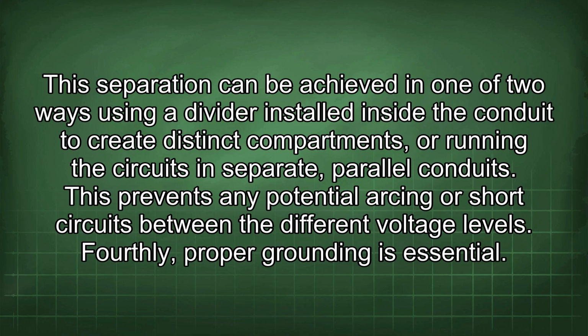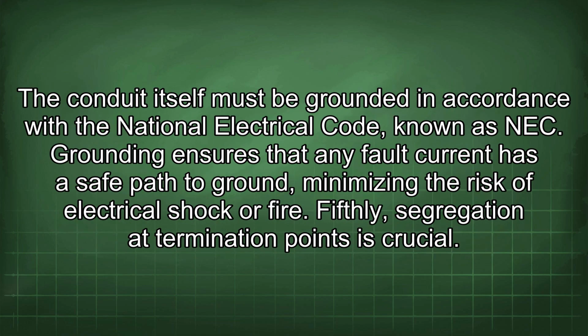Fourthly, proper grounding is essential. The conduit itself must be grounded in accordance with the National Electrical Code, known as NEC. Grounding ensures that any fault current has a safe path to ground, minimizing the risk of electrical shock or fire. Fifthly, segregation at termination points is crucial.